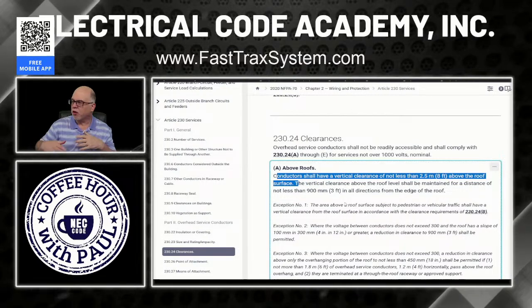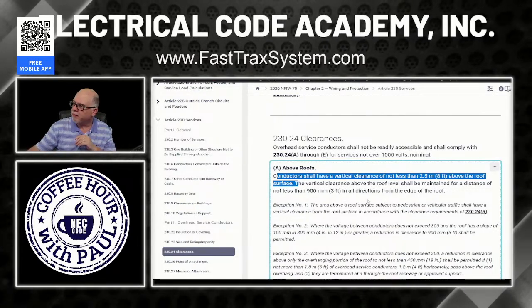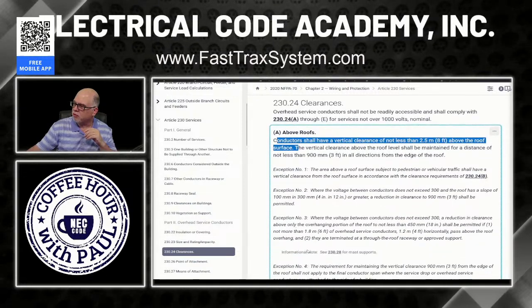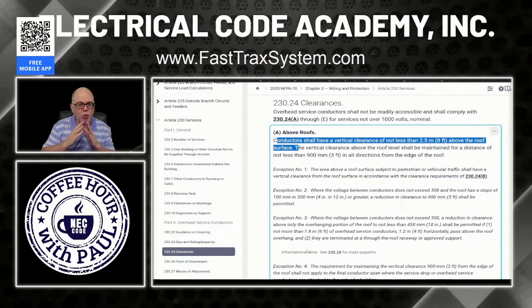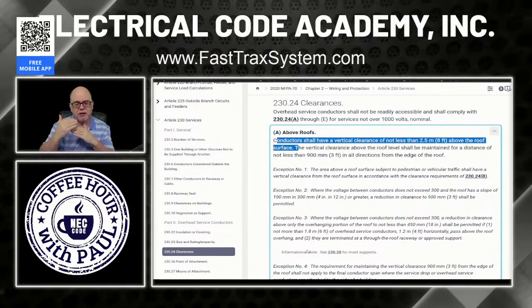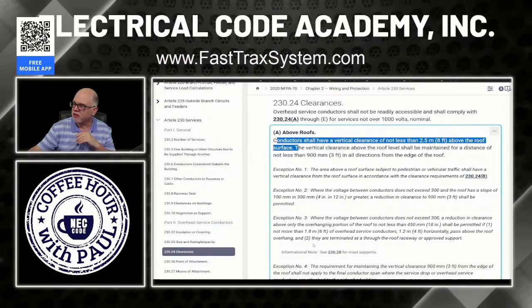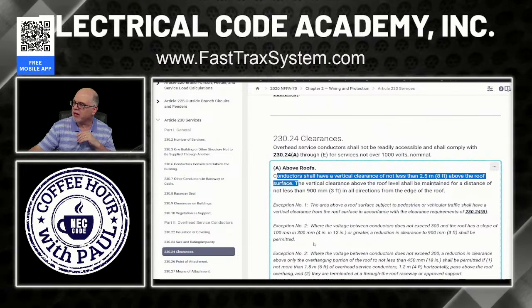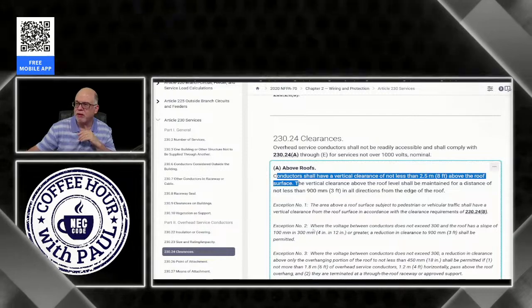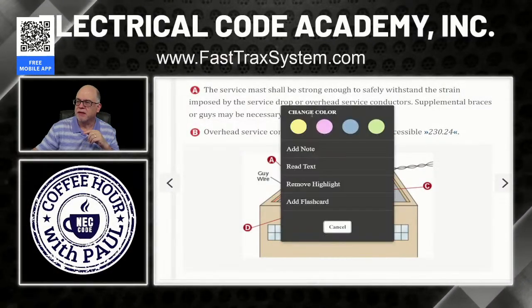Okay. Now, there are some allowances for reduction of clearance. We'll cover that in another video. But basically, it's 8 feet, like you see in the illustration that we had. There are some exceptions, like when you have a roof pitch that is 4:12 or greater, okay, it's pretty steep, then you can reduce it down to 3 feet clearance. But again, generally speaking, 8 foot clearance, unless any of the exceptions apply. You have to make sure that we have that. Okay. All right. So let's kind of get back here. So that's where we went for that. Remember, chevrons, pause, go look it up.